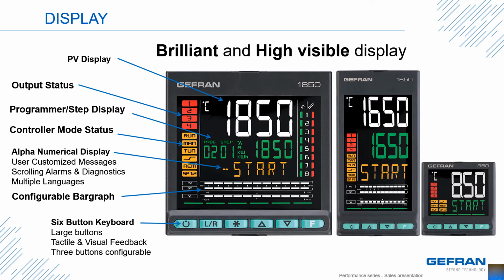The third line of the 1850 showing the word start, this is a user customized display. You can set the customized messaging for alarms or diagnostics. Perhaps it could even instruct the user the equipment is ready to run or load a part or ready to start. Then we have the white bar graphs. These can be set up by the user, but gives you quick feedback on the process status or output percentage. In a motorized valve positioner, it'd give you the position of a valve.